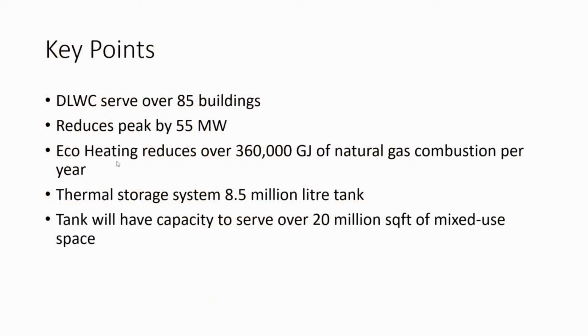To summarize the key points: deep lake water cooling serves over 85 buildings, reducing peak demand by 55 megawatts. Eco-heating, through the heat pump and heat recovery system I mentioned, reduces natural gas combustion by over 360,000 gigajoules per year. The thermal storage tank is an 8.5 million liter tank that can serve over 20 million square feet of mixed-use space.